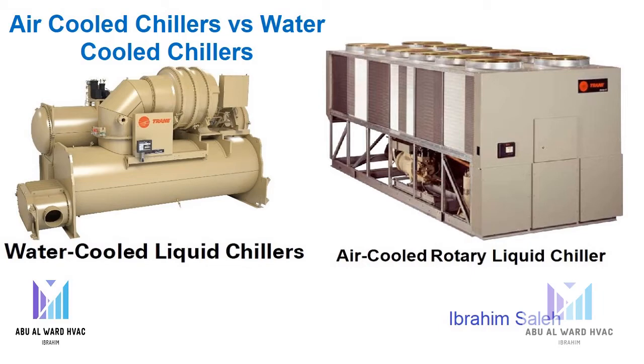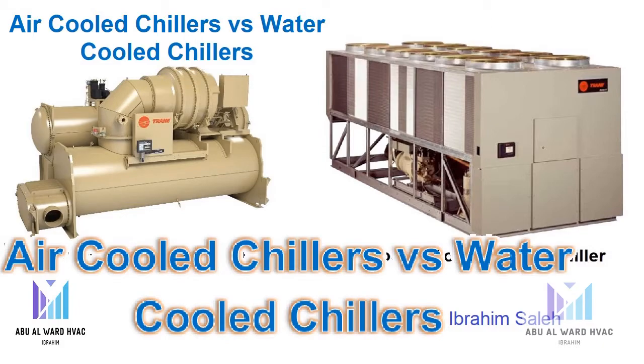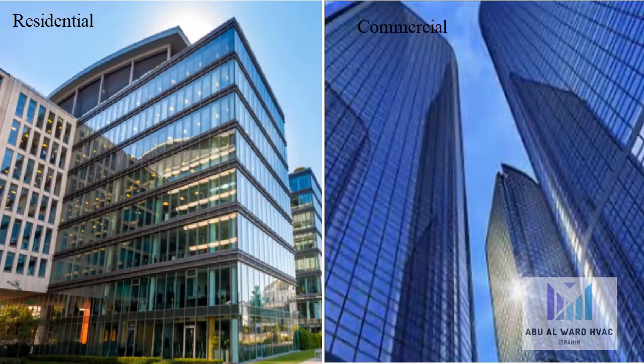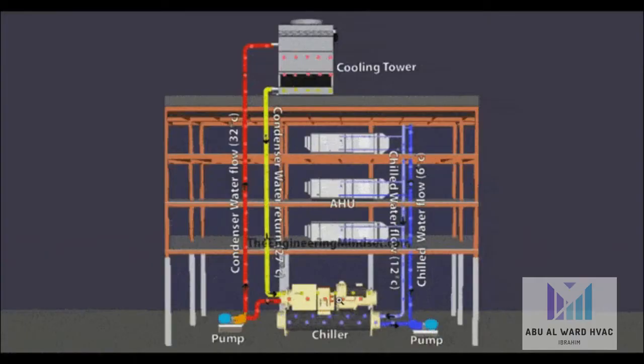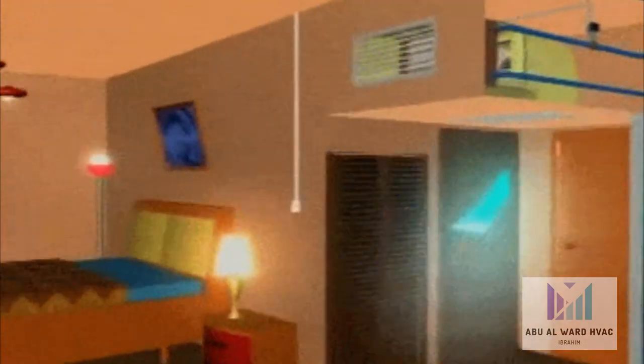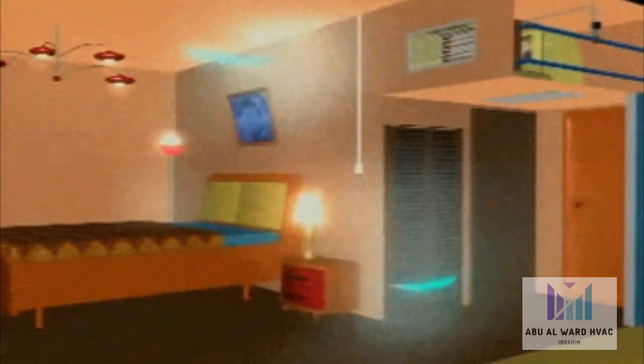In this video I'm going to talk about air-cooled chillers vs water-cooled chillers, and we are going to see some comparison aspects for these types of chillers. Chillers are being used in comfort air conditioning in small or large commercial buildings and for process cooling purposes as well. Chillers play a vital role in chilled water air conditioning system as they serve the chilled water to create the required cooling effect in the space. They produce chilled water or refrigerant, which is transported by pumps and pipes to the cooling coils of conditioning units.